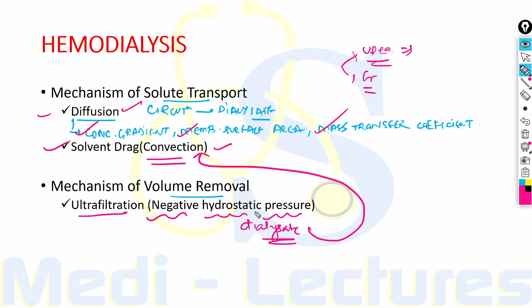Now the dialyzer is a plastic chamber which is most commonly of the hollow fiber type. So the most common dialyzer used is the hollow fiber dialyzer. It is composed of bundles of capillary tubes like this. There are capillary tubes in which the blood runs, and outside the capillary tubes there is dialysate. The filtration occurs through the semi-permeable membrane which separates blood and dialysate. This semi-permeable membrane is made up of biocompatible material, which is polysulfone. Earlier, cellulose membranes were used, which used to activate the complement cascade. Why? Because these were bioincompatible. So now polysulfone membranes are used and these do not activate the complement cascade. There is perfusion of blood and dialysate simultaneously at very high flow rates, which helps in the exchange of solute.